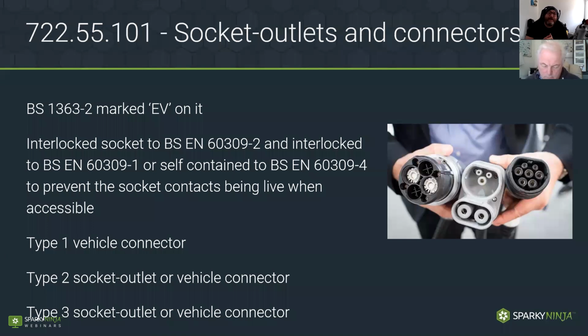But they do manufacture, I think Hager and a couple of others have actually branded them for such a purpose, 1363 socket outlets with electric vehicle markings on the back or on the front, and they're designed obviously to carry larger loads. We think of a typical twin socket outlet is tested at 20 amps. These are sometimes pushed to 25 amps. If you can find one that's pushed to 25 amps as standard, it's just going to be able to tolerate the stress of the larger demand for the longer duration.